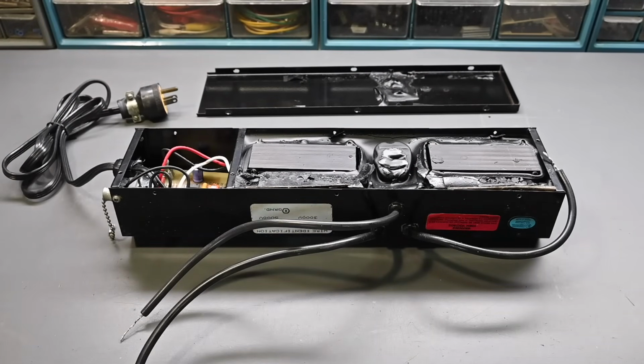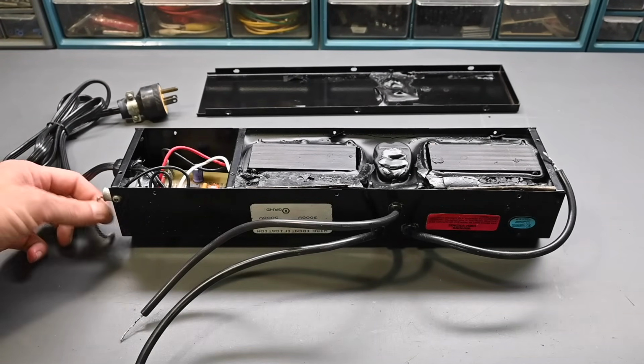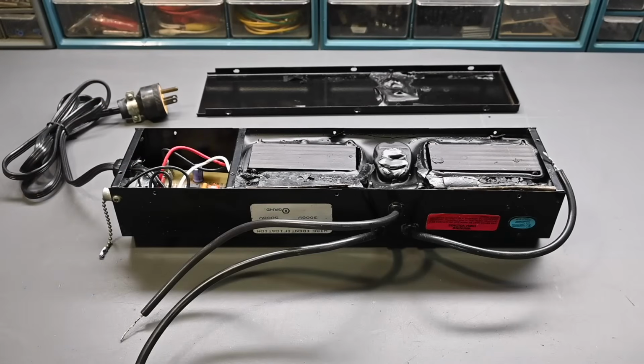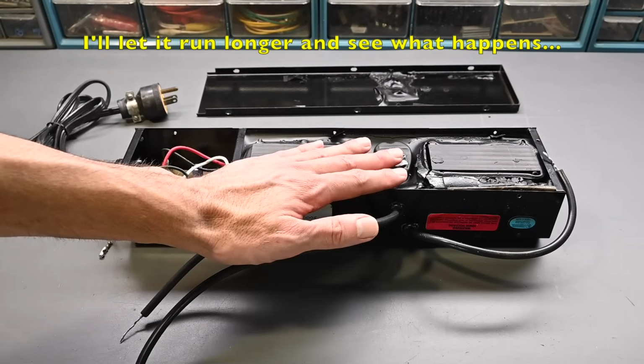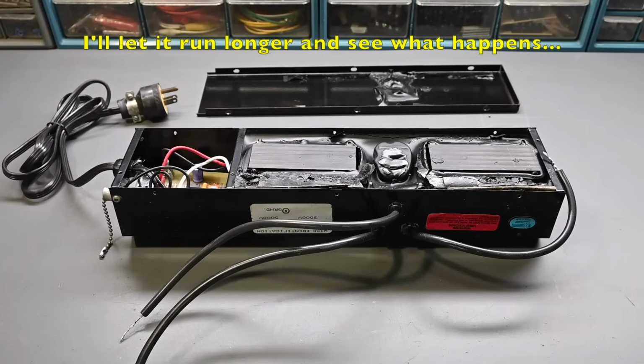What he said the problem is: when you turn the sign on with the pull chain switch, the sign illuminates the way it's supposed to, but part of the sign is supposed to flash on and off, and that section turns off and never cycles back on again. There's nothing wrong with these transformers, they're putting out the right voltage because the sign is able to illuminate, and there's nothing wrong with the neon tubes because they do glow correctly.